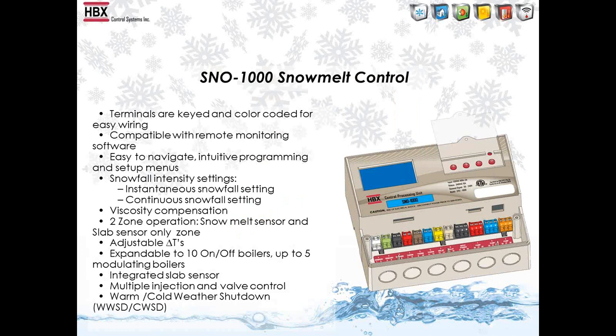So the SNO-1000 was our first snow melt control. Basically the SNO-1000 is like the Tecmar 664 and the 667, I believe. There was a lot of demand back then for fully integrated snow melt systems that would run boilers, run pumps and do all sorts of stuff. And obviously you guys know that the industry has changed with the advent of all the modulating and condensing boilers, so there's no such need for such big controls anymore. But we'll go over this control a little bit.